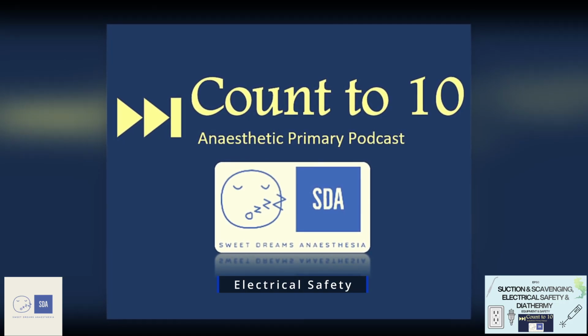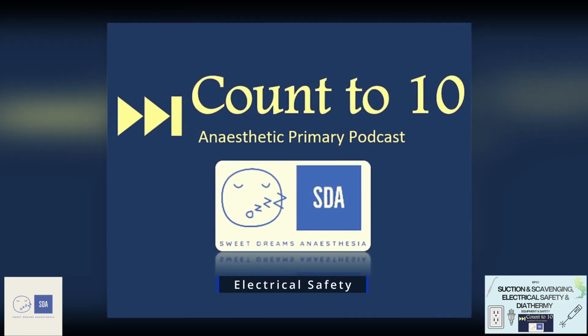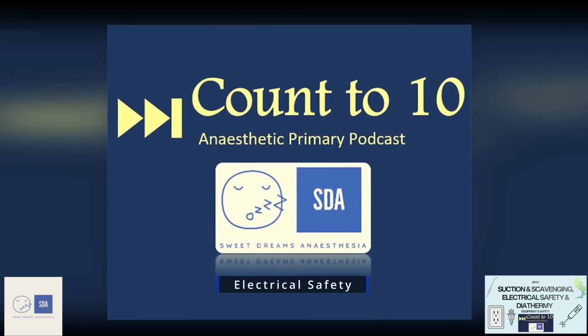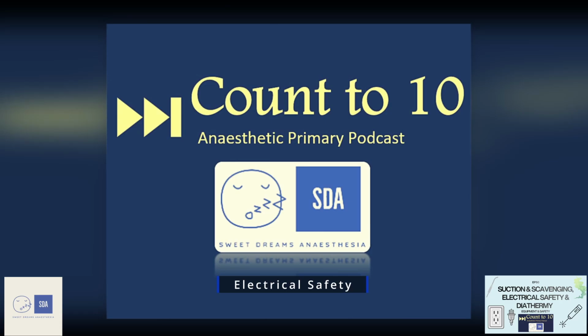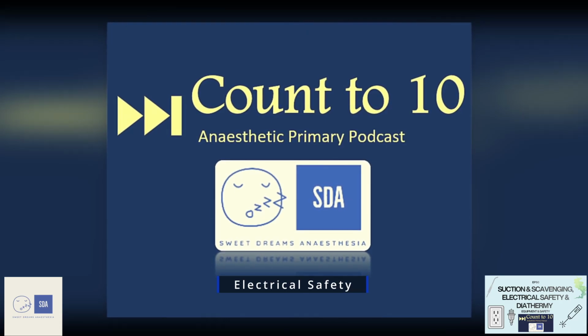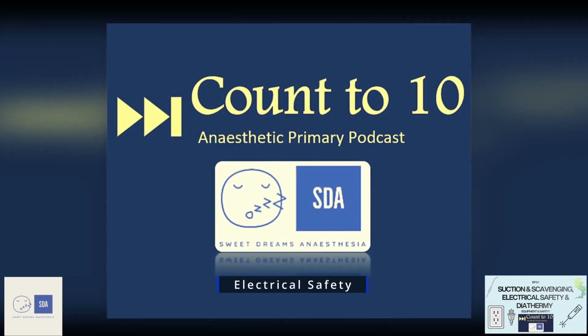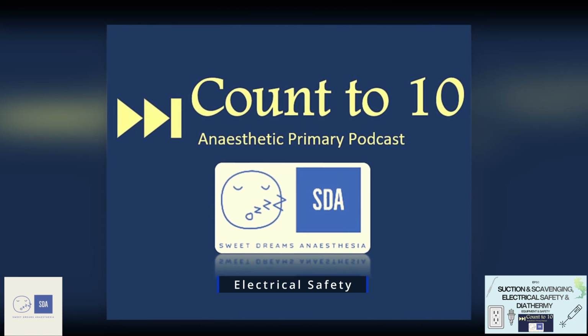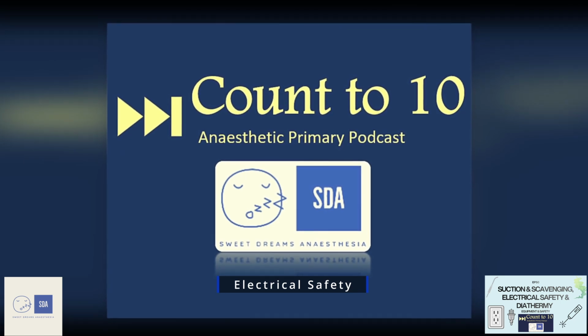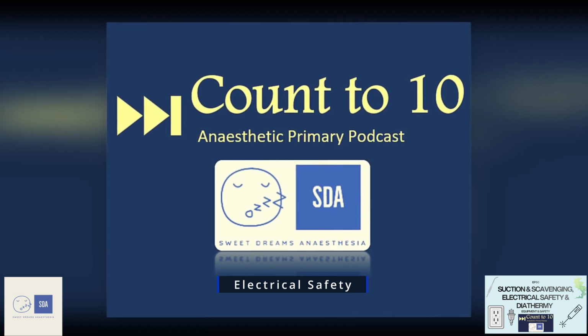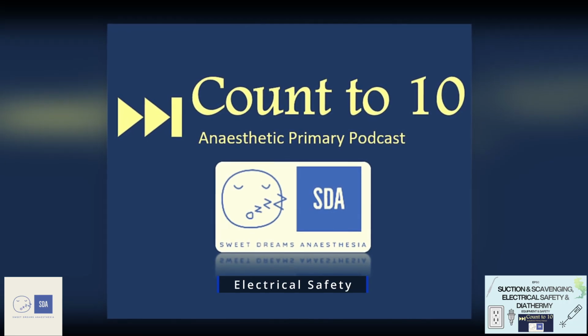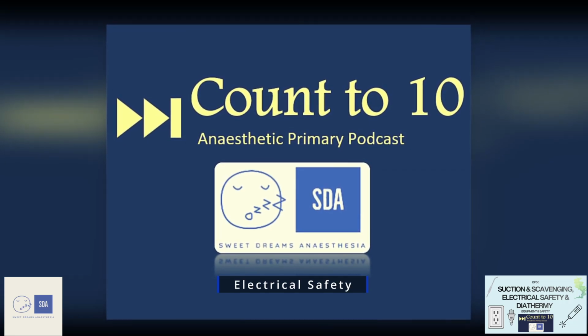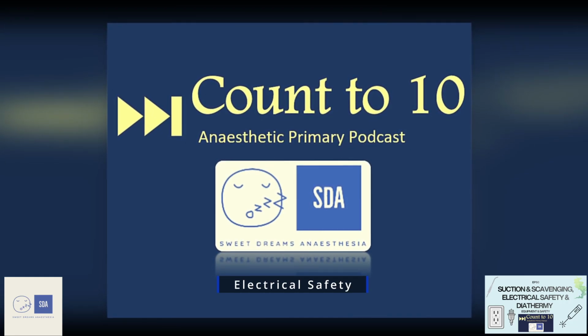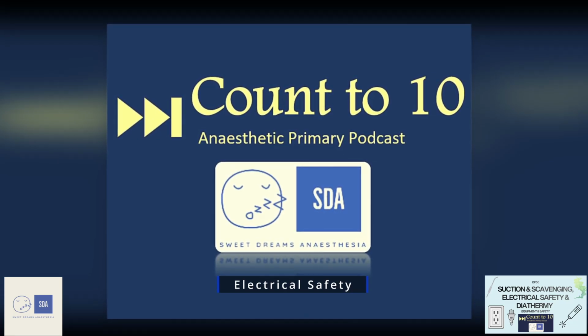Then with line isolation monitors, this is slightly trickier to understand, but what it's actually doing, I think, is very cool and really smart. It's creating, as its name sounds, a circuit which is isolated from Earth, a so-called floating circuit. The floating circuit refers to there being two circuits: a primary circuit which is part of the main circuit getting power from the power station, and then a secondary circuit which is not actually connected to the main supply.